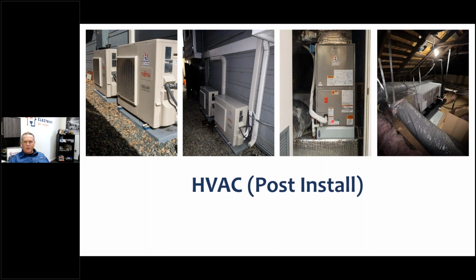In the downstairs suite, we changed the assembly of this unit, as the old one had the return air duct attached directly to the side of the furnace. We built a mixing box at the bottom that established the location for our MERV 13 filtration system, increased to an 18-inch duct, and redid the supply ducts and everything on top.